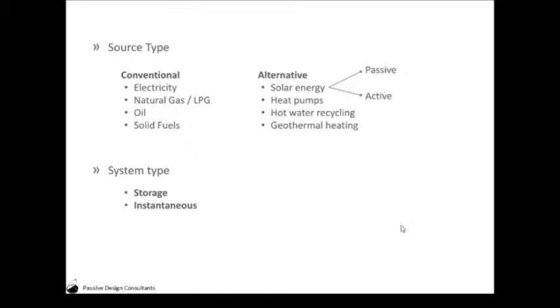Hence, the storage unit has to meet its insulation requirements so that the storage losses are minimized. At the same time, the instantaneous systems are where the water is heated and instantly supplied to the taps, to the water requirement zones. In these systems, the distribution of hot water should be designed so that the transmission losses or the pipe losses are minimum. So the hot water section of ECBC basically deals with all these requirements.